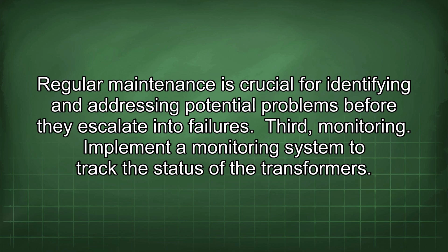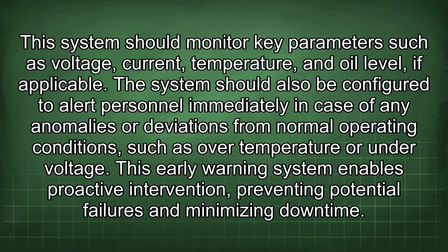Third, monitoring. Implement a monitoring system to track the status of the transformers. This system should monitor key parameters such as voltage, current, temperature, and oil level, if applicable. The system should also be configured to alert personnel immediately in case of any anomalies or deviations from normal operating conditions, such as over temperature or under voltage. This early warning system enables proactive intervention, preventing potential failures and minimizing downtime.